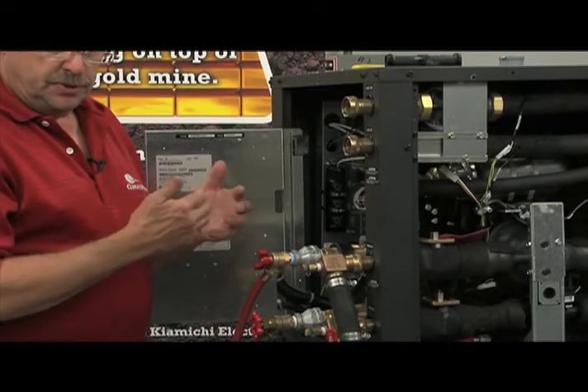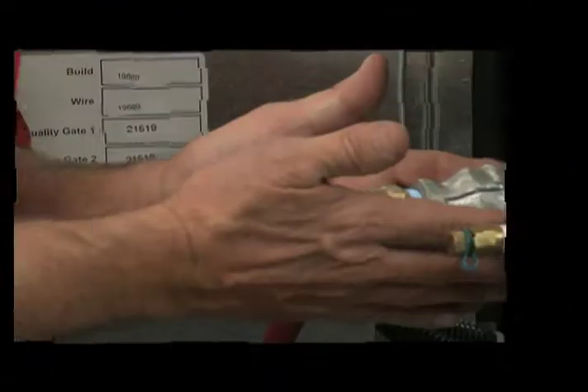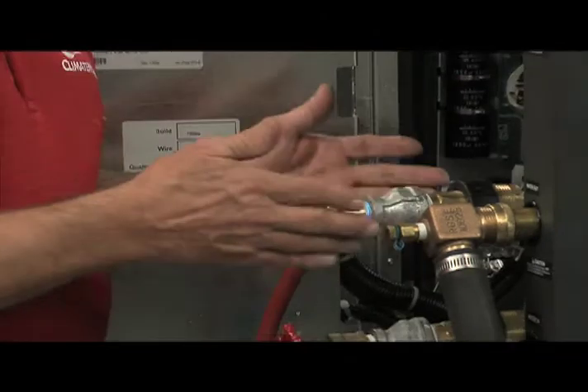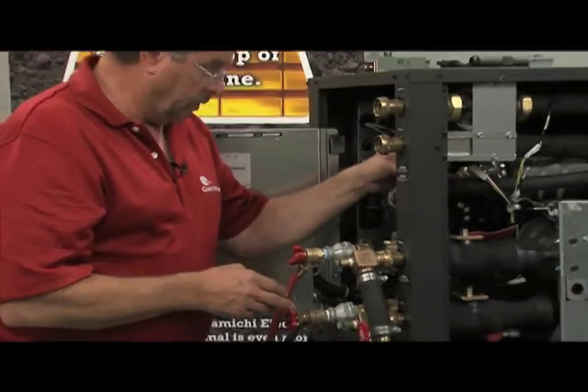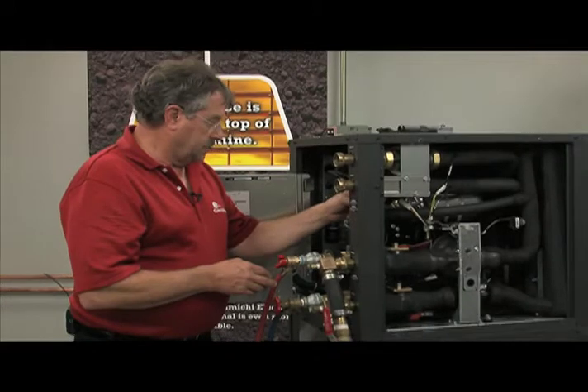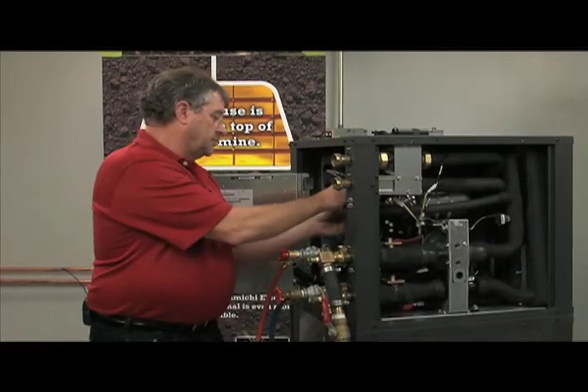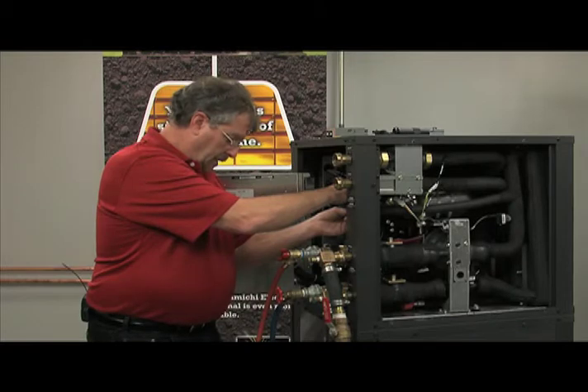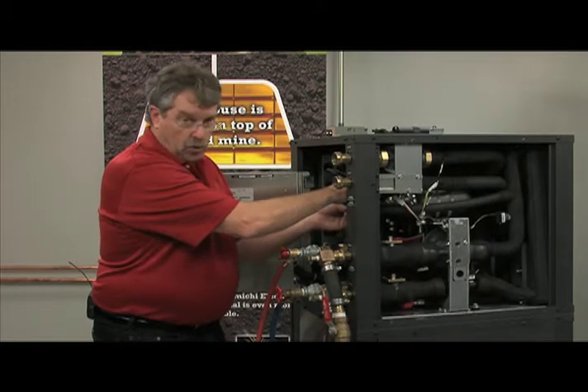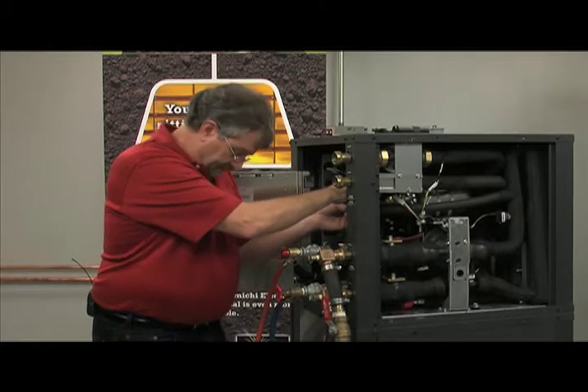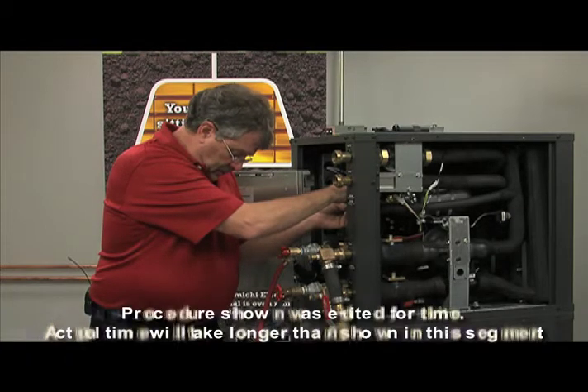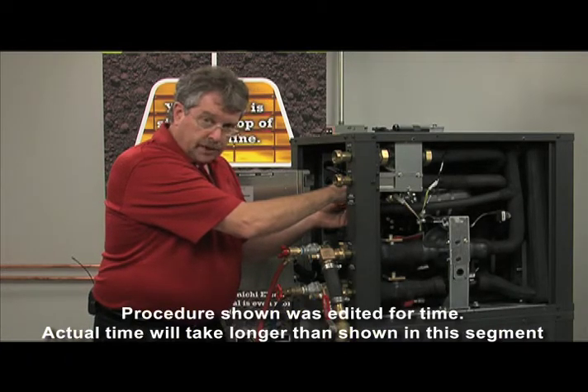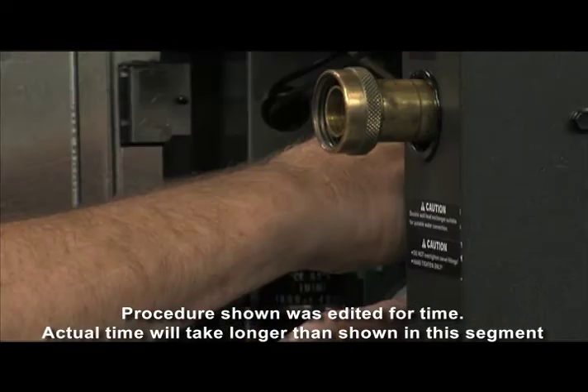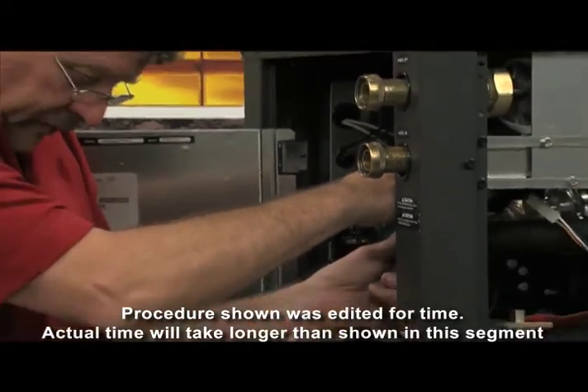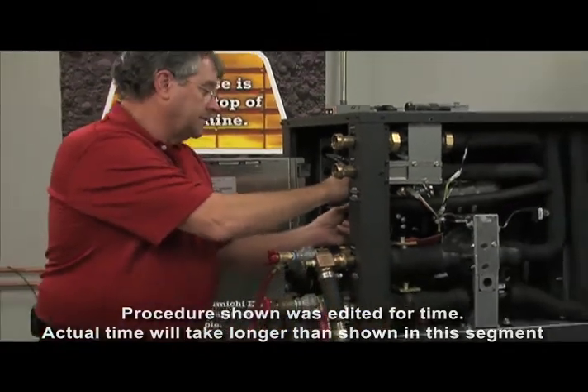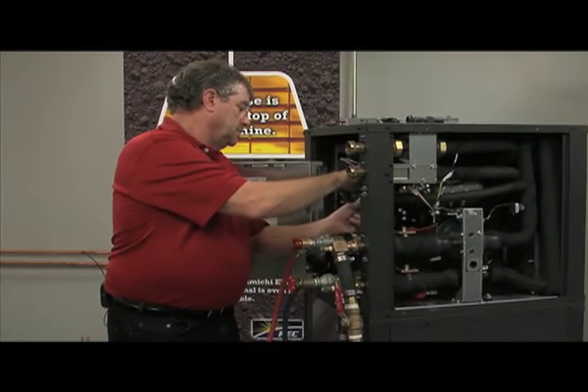Make less of a mess when you pull these clips to replace these sensors. So it looks like we've got the bulk of the fluid, or at least the pressure, moved out of the system there into our captive bucket. But one of the things I'm going to do is depress our Schrader fitting here at the expansion tank. That'll allow some air in, and sure enough, we're getting more water, so we're ventilating it, just so that we can kind of control the mess to a large degree. All right, it looks like we've gotten all the fluid out of there that it's going to give us, having this ventilated. I'm going to go ahead and put the cap back on just so I don't misplace it.